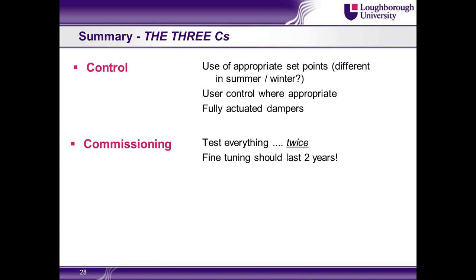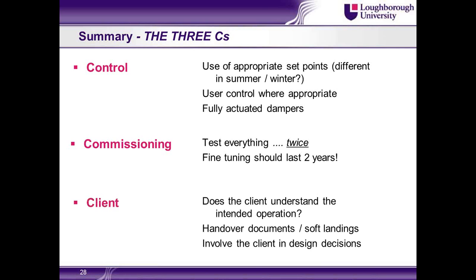You know, make sure that the dampers are opening when they are intended to and to the extent at which they are intended to. And fine-tune that. So if they're opening too wide too quickly, then reduce that and tweak that over a period of years and you will bring down the energy consumption. That's what we did at Coventry University Library. Spent 2 years fine-tuning it, and we were able to drive the energy consumption down even further.